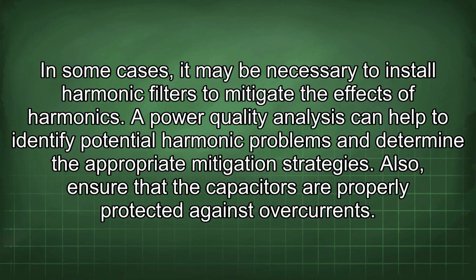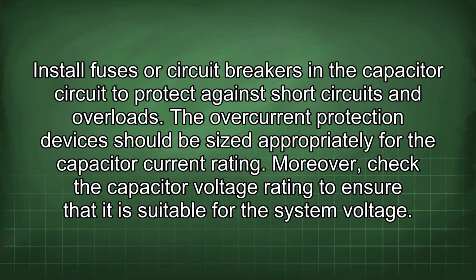Also, ensure that the capacitors are properly protected against overcurrent. Install fuses or circuit breakers in the capacitor circuit to protect against short circuits and overloads. The overcurrent protection devices should be sized appropriately for the capacitor current rating.